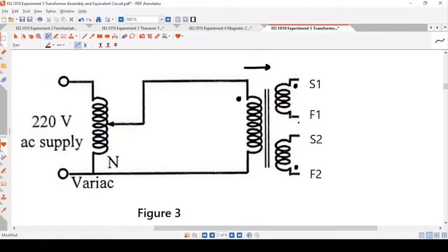Our objective is, depending on the connections we make, to find the voltage across different pairs of points. If we connect these two terminals, find the voltage; if we connect another two, find that voltage. We do a permutation combination of every two connections, but we must be careful not to connect two terminals of the same winding -- only terminals between the two different windings.